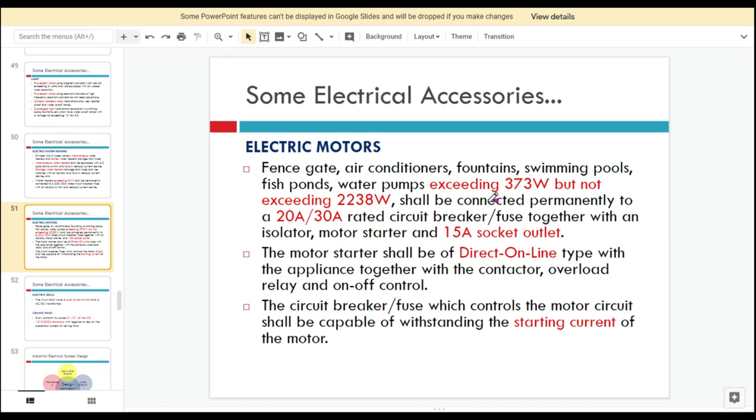For motors exceeding 373 watts but not exceeding 2238 watts, we can connect them with a rated circuit breaker or fuse of 20 to 30 amps, together with an isolator, motor starter, and a 15-amp socket outlet. The motor starter shall be of the direct-online type, together with a contactor, overload relay, and on-off control.